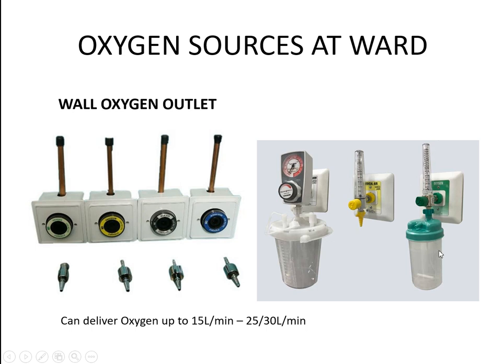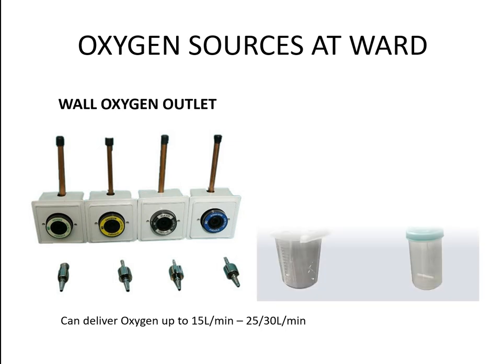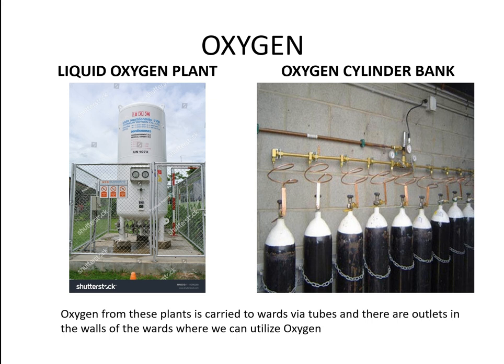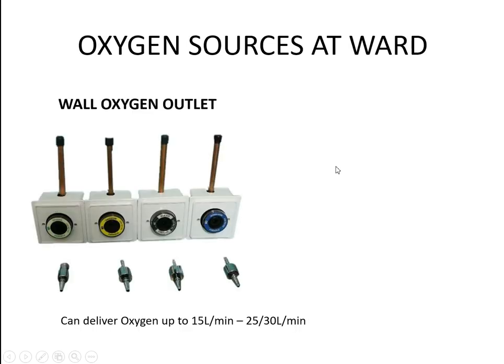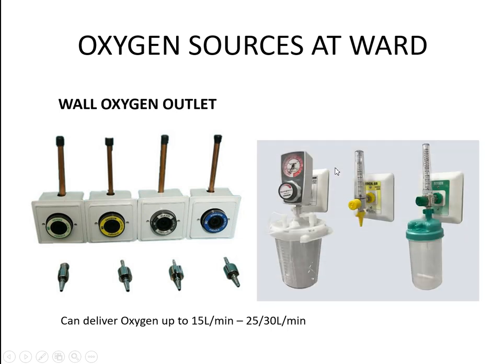Apart from this gauging system, here you can see a bottle-like thing. This is called the humidifier chamber, and it contains distilled water. The oxygen provided to the patients is vaporized by these devices. So what we are getting from this total device is humidified oxygen, which will moisten our airways, right? So, in summary, these wall oxygen outlets get oxygen from the oxygen plants I mentioned previously. From these plants, oxygen is carried via a tube system, and you can see part of the tube system here, to the wards. Here we can use oxygen by connecting the wall oxygen regulator, and this end is connected to the patient, right?